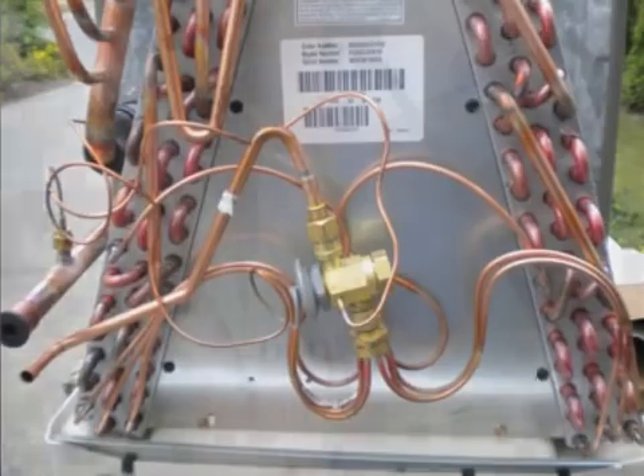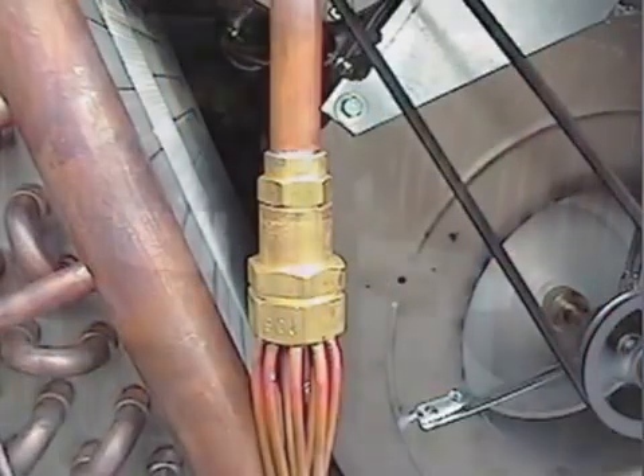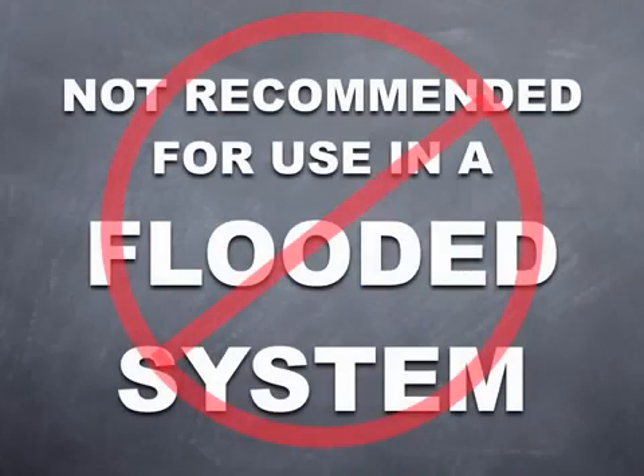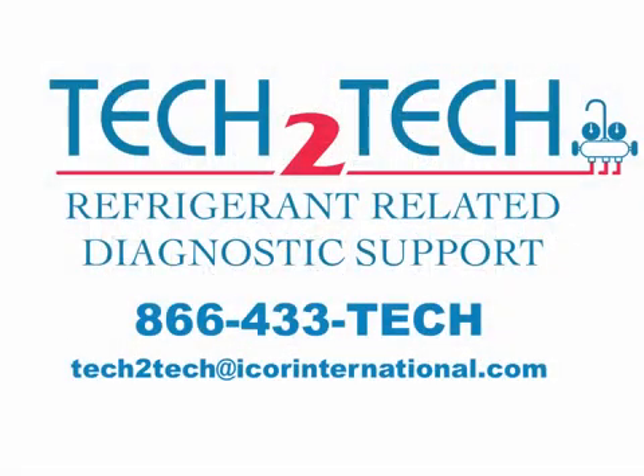Requirement 2: NU-22B is designed for use in systems utilizing direct expansion metering devices such as TXVs, fixed orifice, or cap tube. Requirement 3: it's not recommended to use this product in a flooded system. If you have a unique application you're considering for retrofit, please consult with an Icor tech support member before proceeding.